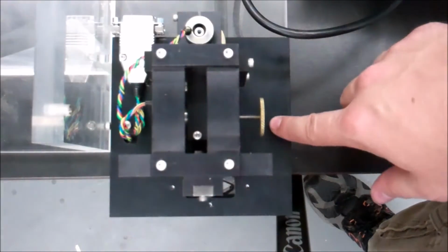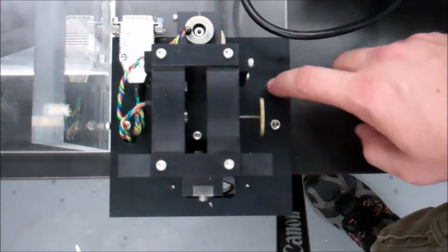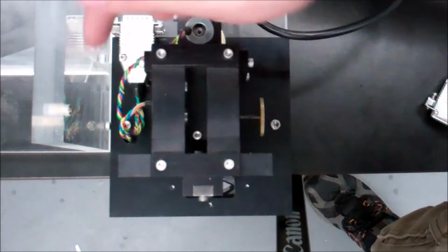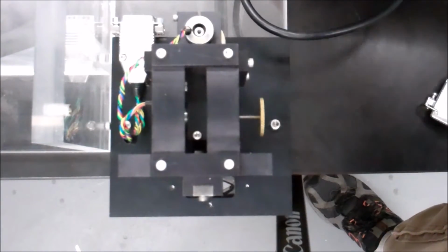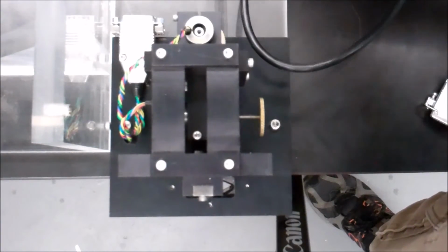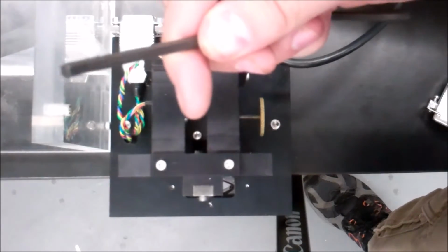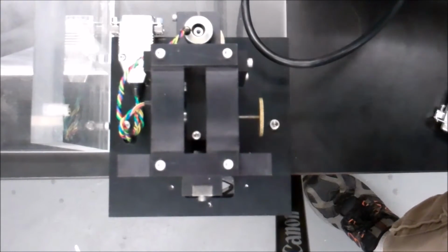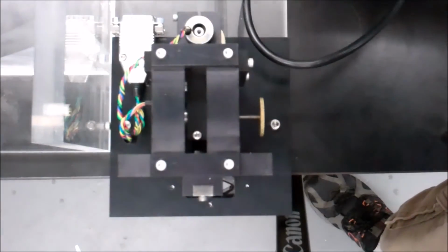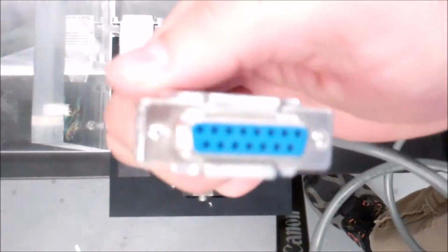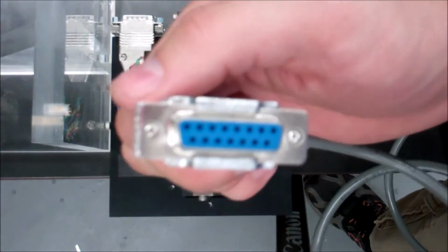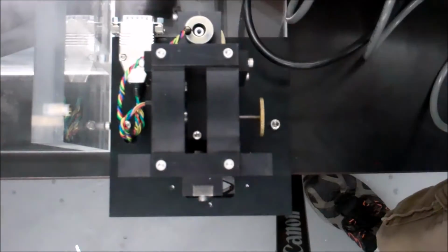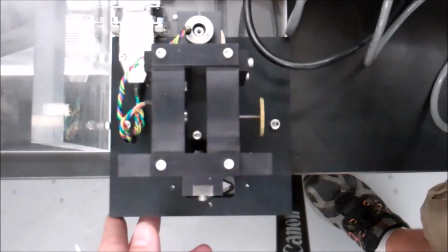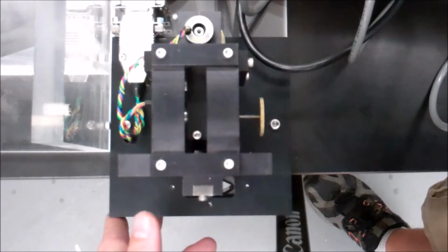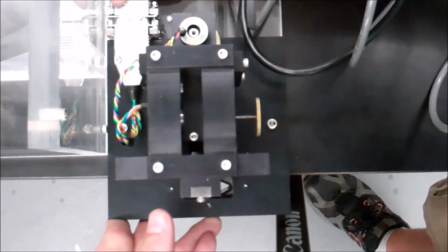So when you're doing the lift calibration, you go ahead and put it upside down and screw it in these two holes using the same Allen wrench that you had taken it off with from the plastic acrylic piece here. And now you're going to take the other end of the wire that you hooked into the back of the digital pressure transducer and force balance system, and you're going to go ahead and connect it to the force balance itself.